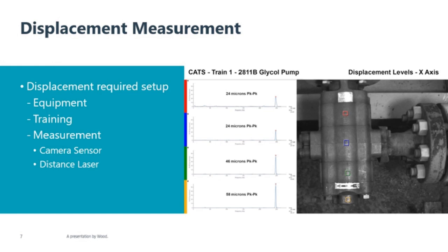This is then very useful for calculating total displacement within a vibration. And it's handy on this image. Here you can see 4 measured points along the casing of a pump. It's showing the maximum displacement and frequency graph. It is displacing 24 micron at the drive end and 58 micron at the non-drive end. It's got quite the wobble on the go, and the frequency matches the gear meshing frequency. So as you can see on that frequency graph, there's probably a lot more there, but because there's such a great movement at the meshing speed, that's what's prominent, and it's a big peak.